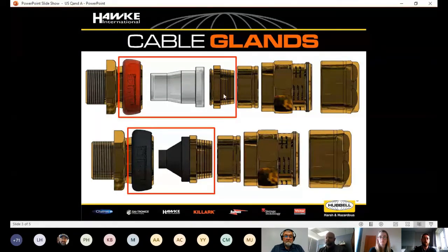4 components. One being a resin stop spigot. That's got a seal inside that stops any resin pouring down the inside. If you were to specify the express liquid resin, you would get the clear compound chamber and you would get a red deluge boot. Then you would also pick whether you want a putty style resin or the liquid style.